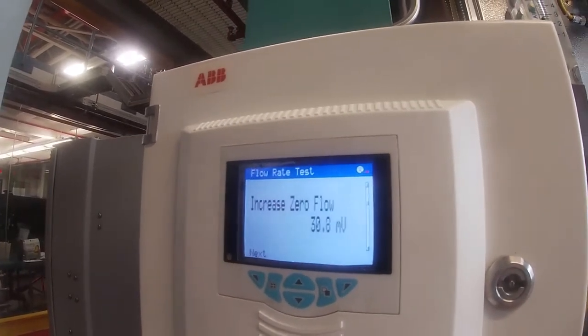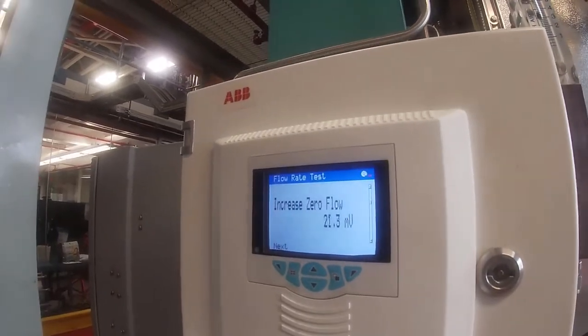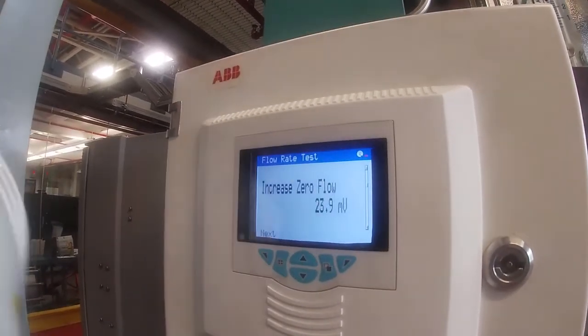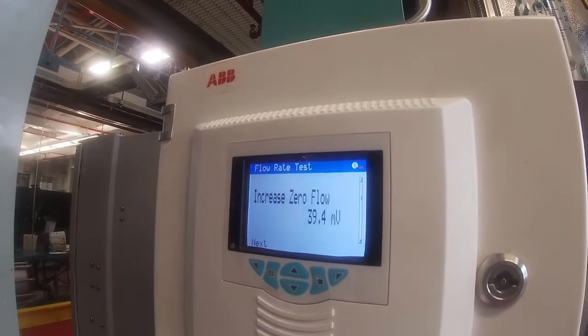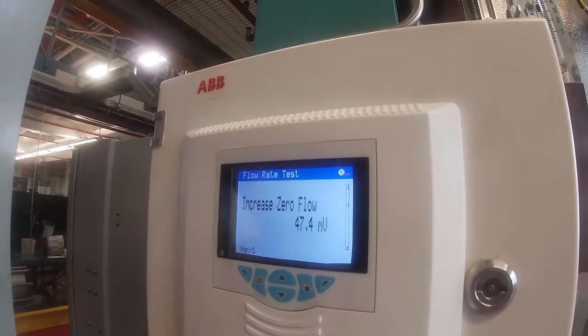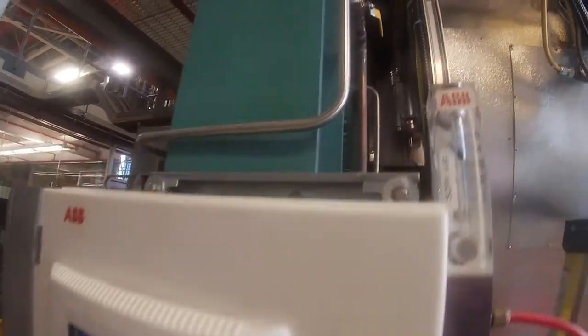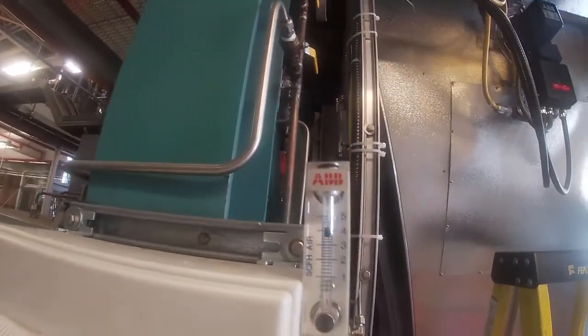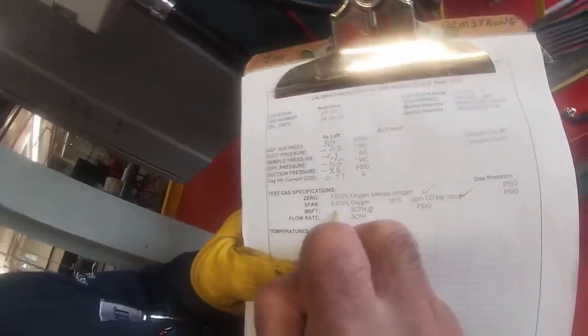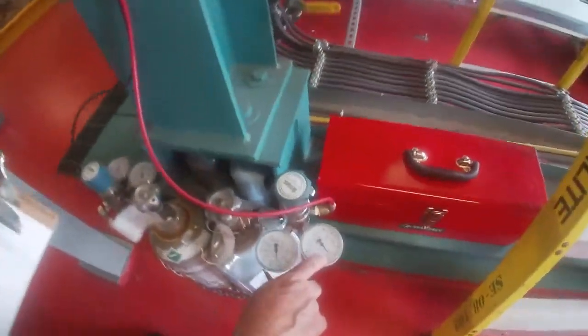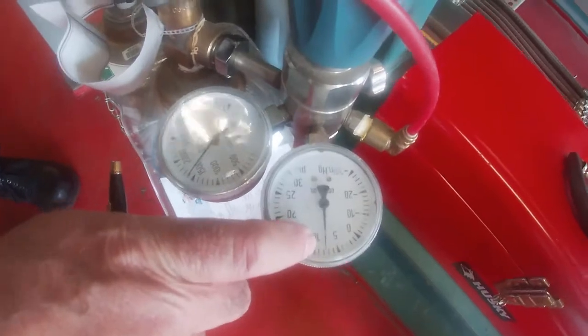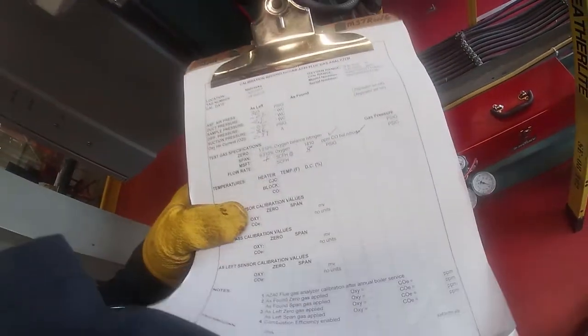There it goes. Okay, and so our minimum flow sample test is somewhere around 4. And that's about where that 47, 51, something like that is sitting. So the minimum flow sample test is 4. And the pressure on the gauge is sitting at almost 8, up at 8 psi. This is just all for reference purposes.